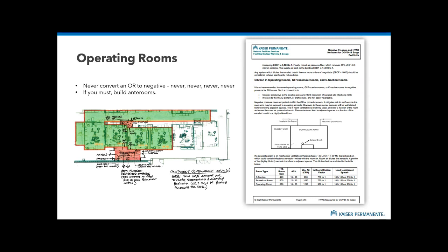The right way is, by the way, if you have aerosols in an OR and you need to protect workers in the hallway, then you keep the OR positive, but you build negative pressure anterooms at all the doors. So we had a couple hospitals look at proposals to do this. That's what that picture is. None of them actually did, and I'm grateful for that.